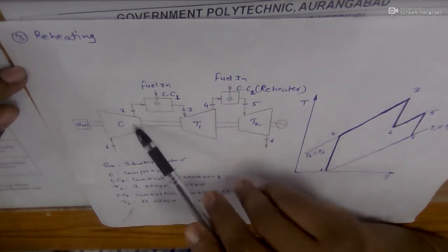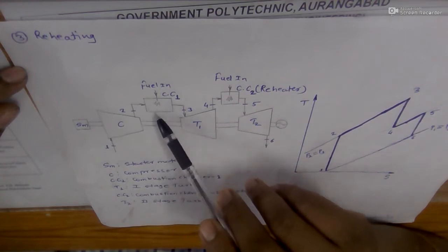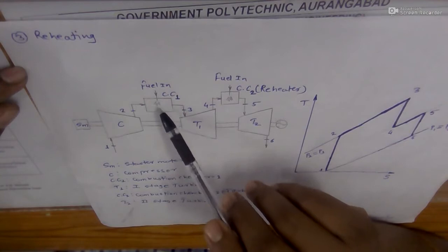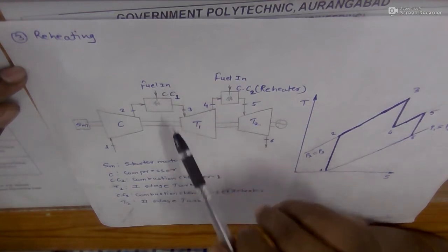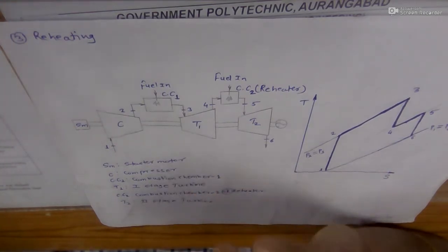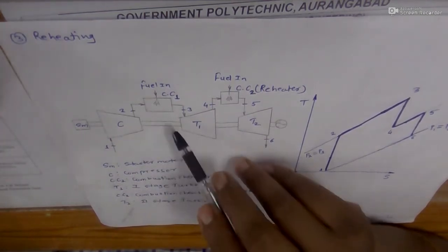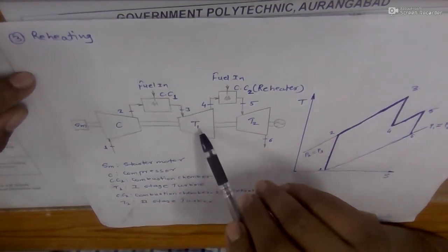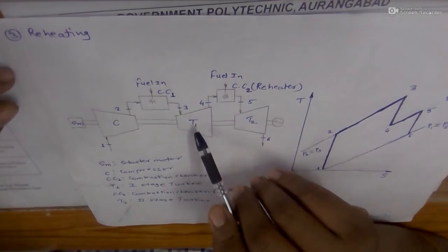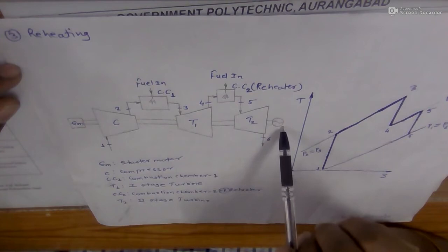Fuel is sprayed on that heated compressed air through the fuel line in combustion chamber 1, and as soon as the conditions for combustion are favorable, combustion takes place. The high pressure gases are allowed to expand in turbine 1. Turbine 1 rotates at full speed, taking the load of turbine 2, the compressor, and the generator.